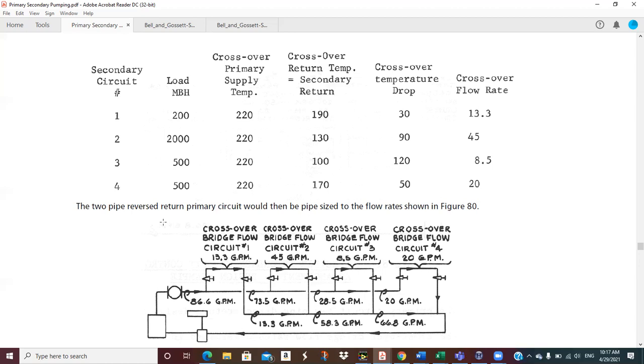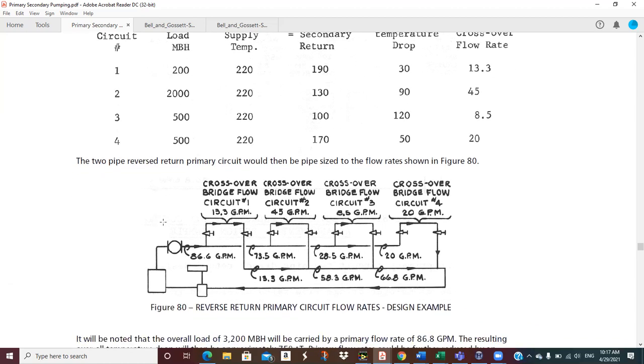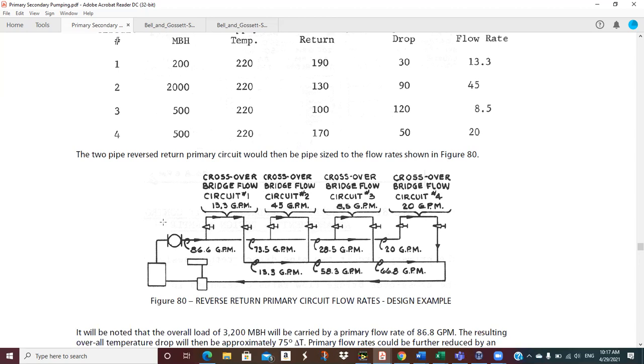He says 86.6. Well, he isn't right, is he? He can't add. I'm sorry, I disagree with him, but anyway, I'm going to use my number. So let's see, what do we want to do here? What's the delta T, or what's the return temperature to my boiler? If I add up all of those loads, it's 2 million, 3 million, that's 3.2 million BTUs an hour. So 3,200,000 divided by the flow rate, divided by 500.